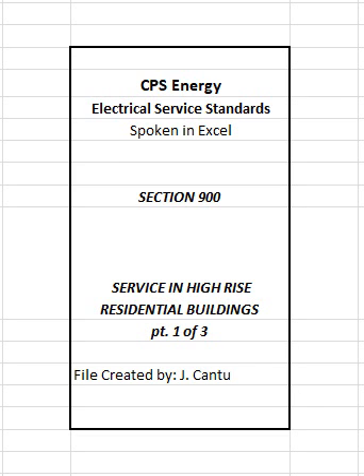902 Secondary voltage distribution system. Refer to Figure 901. This type of installation typically involves a three-phase CPS Energy transformer located outside at ground level supplying customer-owned service equipment located outside or inside of building. Customer-owned service equipment supplies riser feeders to CPS Energy-approved meter rooms located on every third floor and also supplies all house loads within building. Note: house loads shall be metered separately and such metering equipment shall be located at the customer service equipment location.